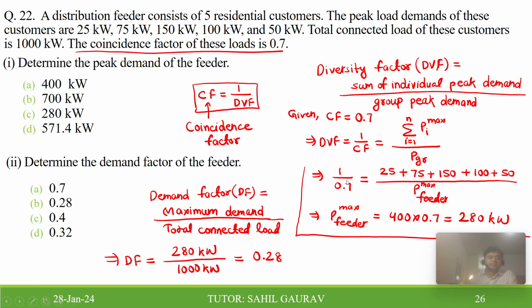So you get the diversity factor, and diversity factor is the ratio of the sum of individual peak demands divided by the group peak demand. The sum of individual peak demands is 25 plus 75 plus 150 plus 100 plus 50, and from here we can find the group peak demand. So the group peak demand will be 400 multiplied by 0.7, which gives you 280 kilowatt. So the peak demand of the feeder is 280 kilowatt.